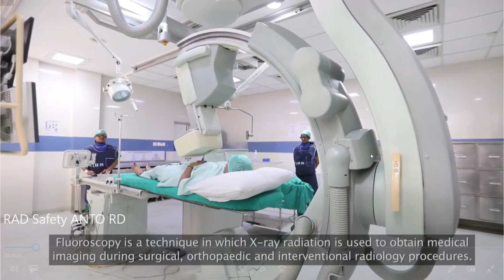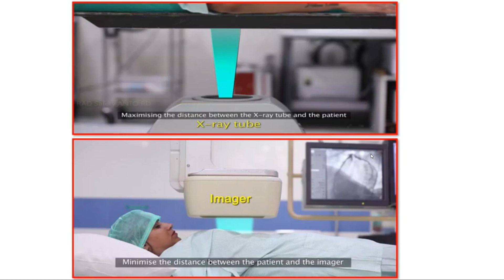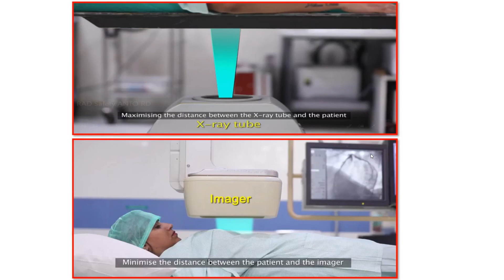Also, you have to be there at least 15 minutes before the procedure starts, because the procedure will be started by a surgeon and other people, so they will come at that time. Our duty is to go and see the space available for moving or placing the machine, or in case of mobile X-ray, to place the cassette. So we have to take time to analyze this. Even the position of the tube, when it comes to fluoroscopy, you have to ensure that you maximize the distance between the X-ray tube and the patient, and minimize the distance for the image intensifier. If you see here, see the distance and the distance here. This will help reduce the radiation dose and also increase image quality.